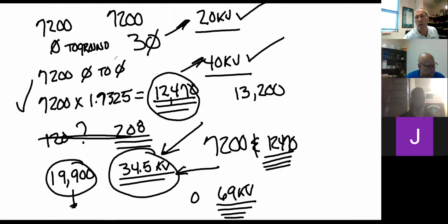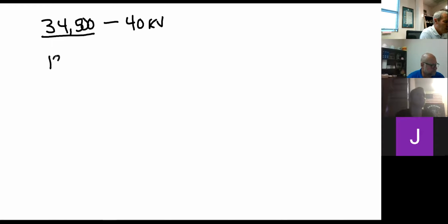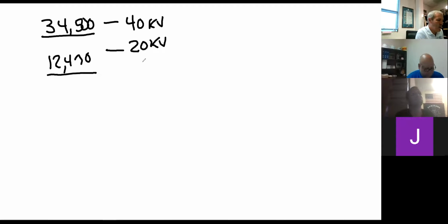and let me clear the screen off. Clear all drawings. So the highest potential, 34,500, that we could work on, and we had a 40 kV glove. All right, that's one voltage that we worked. 12,470, and we had another glove that we worked with that. I can tell you right now, between the 12 and the 20 kV, you've got what, 7,600 volts of extra protection there, right? How much do you have on 34.5? A lot. 5,500. That's a 40 kV glove. You're working at 34.5 kV.